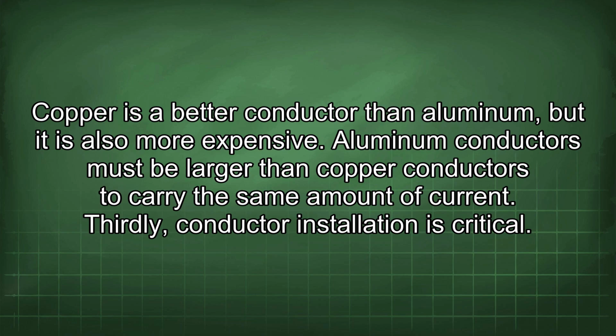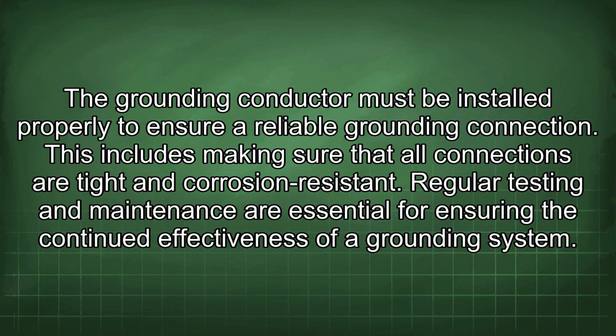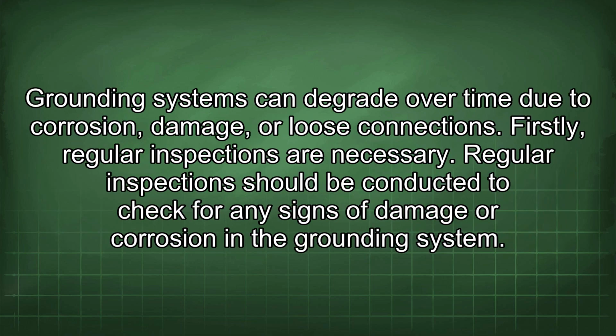Thirdly, conductor installation is critical. The grounding conductor must be installed properly to ensure a reliable grounding connection. This includes making sure that all connections are tight and corrosion resistant. Regular testing and maintenance are essential for ensuring the continued effectiveness of a grounding system. Grounding systems can degrade over time due to corrosion, damage, or loose connections.